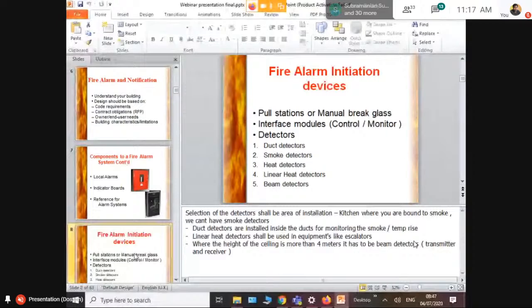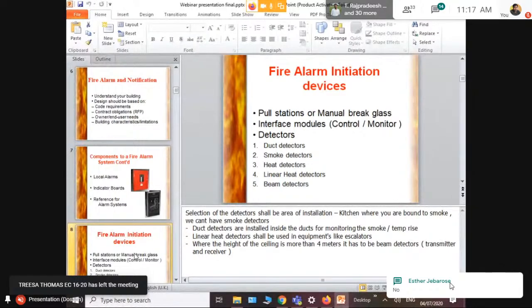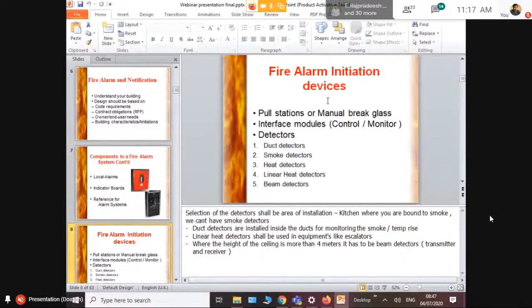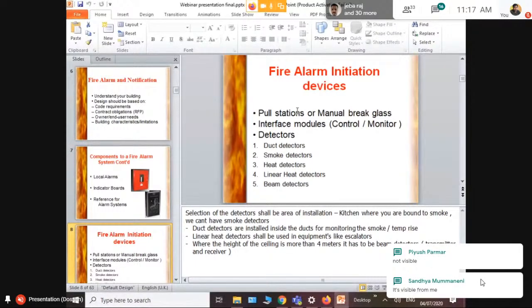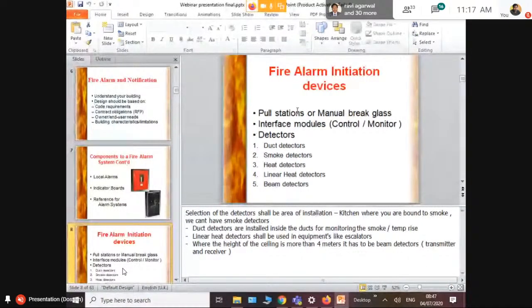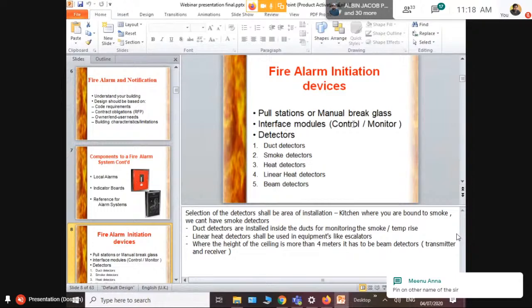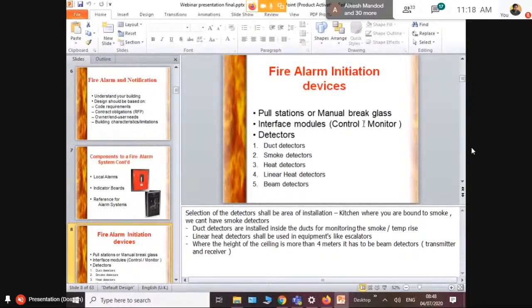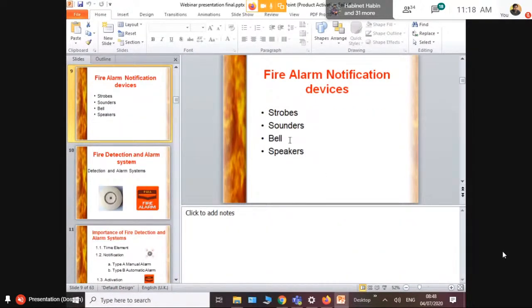Now we'll see the input devices, and I'll explain one by one how they work. The first is the initiation devices. The first device we are going to see is a pull station or a manual break glass. We would have seen this in shopping malls, a red colored box which we can pull, so that it is a direct fire alarm and people will evacuate the building. Then interface modules. There are two types of modules: a control module and a monitor module. Control is where we give a signal so that the equipment is controlled. Monitor is where we monitor that the equipment is functioning: strobes, sounders, bells, and speakers.